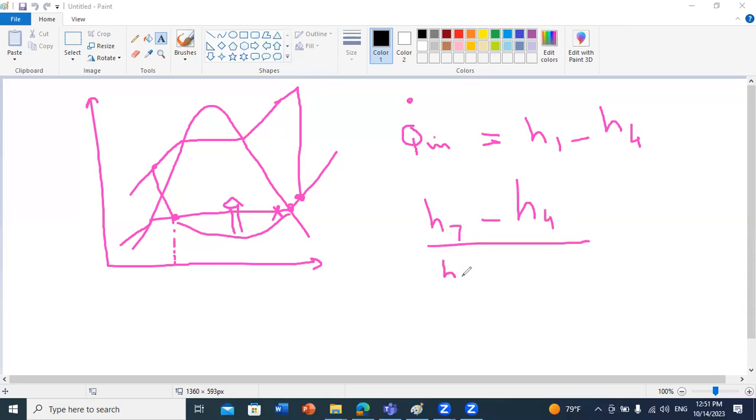So increasing the value of H1 a lot will not be good, because if you do a lot of superheating and exit your evaporator at a high value of H, this will maybe reduce the possible power within your compressor. So you should optimize the ratio here.